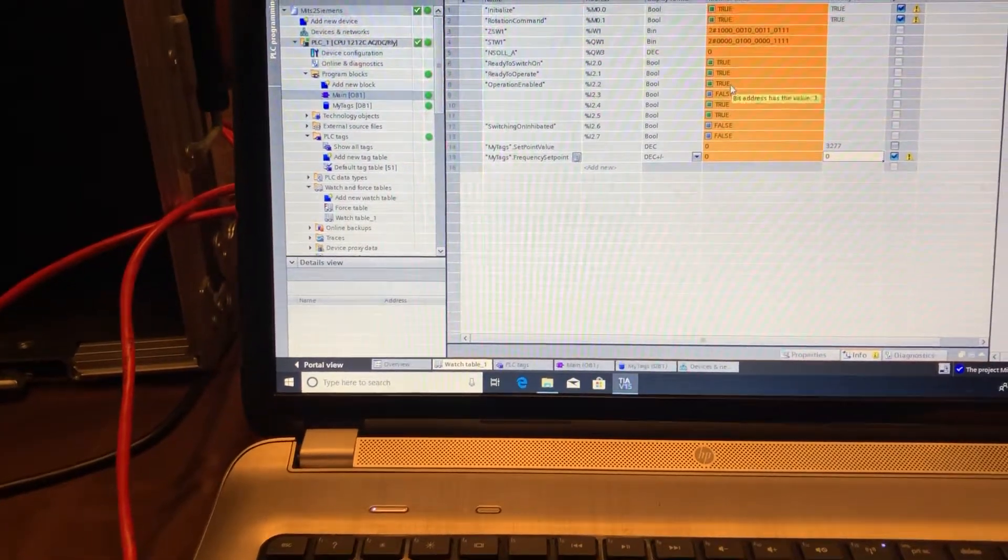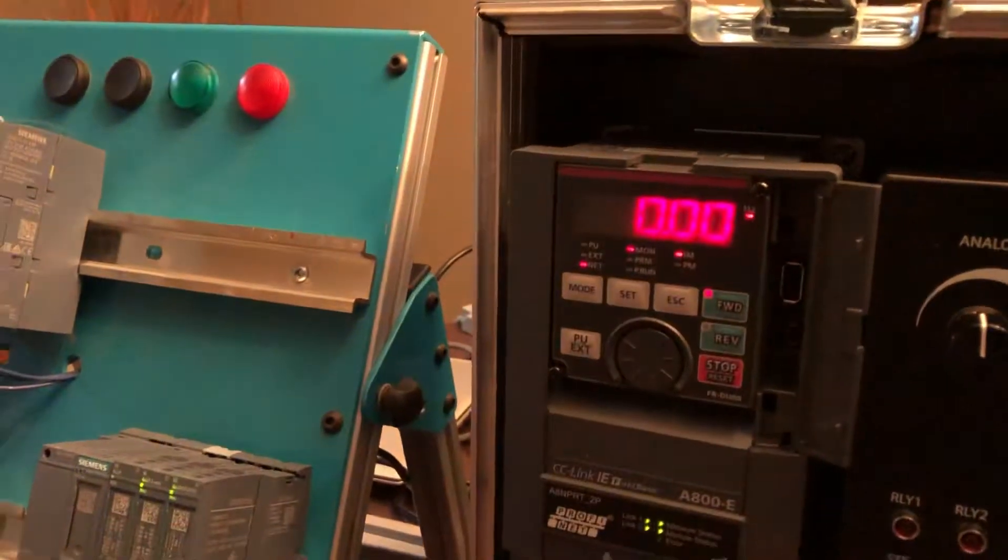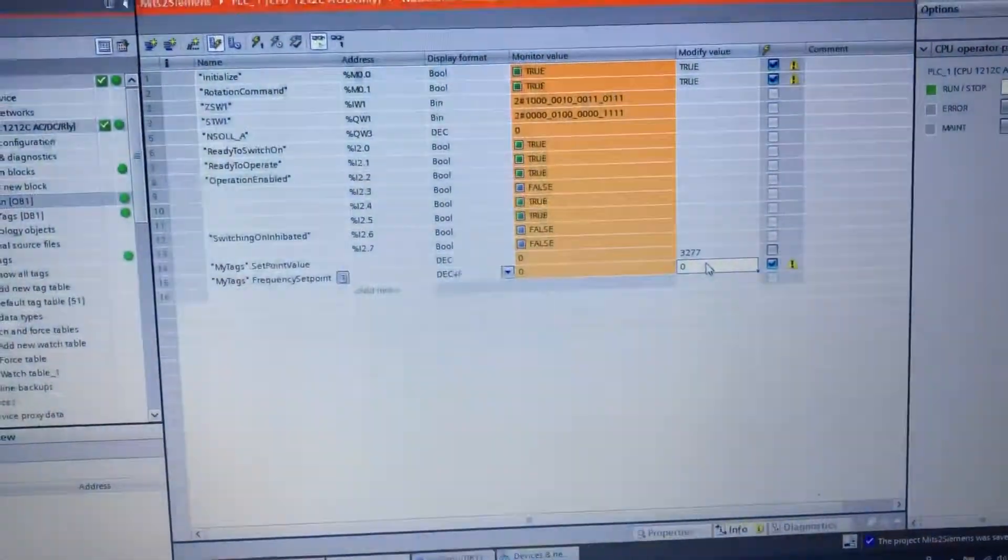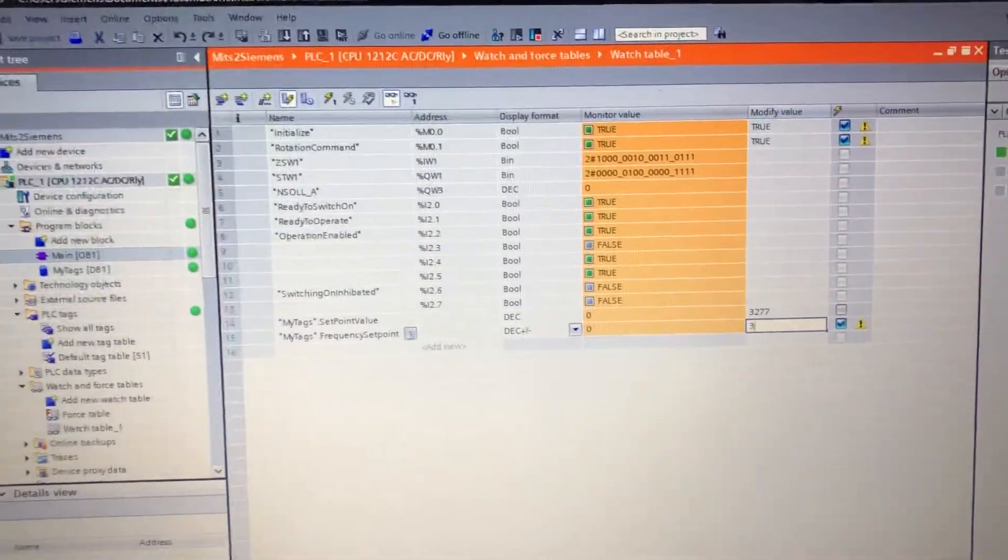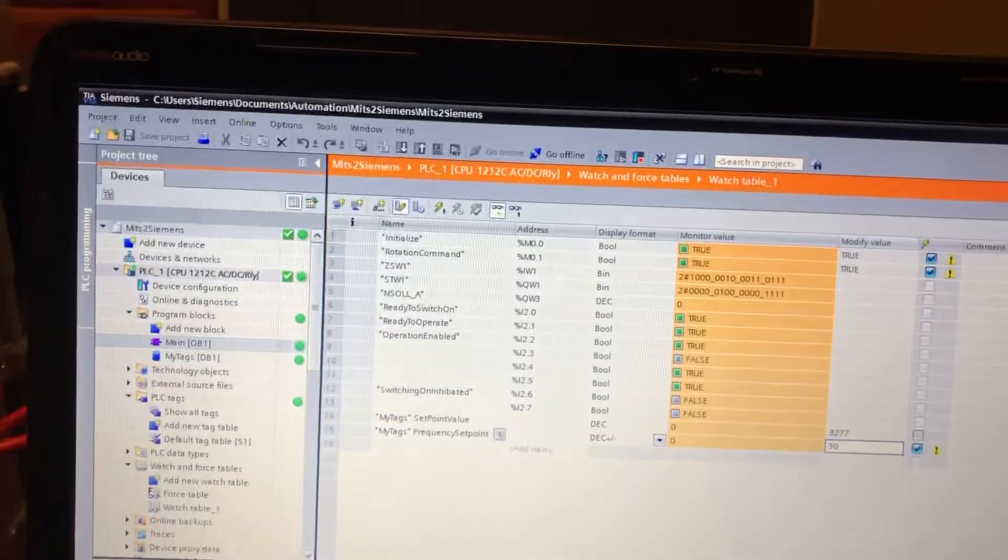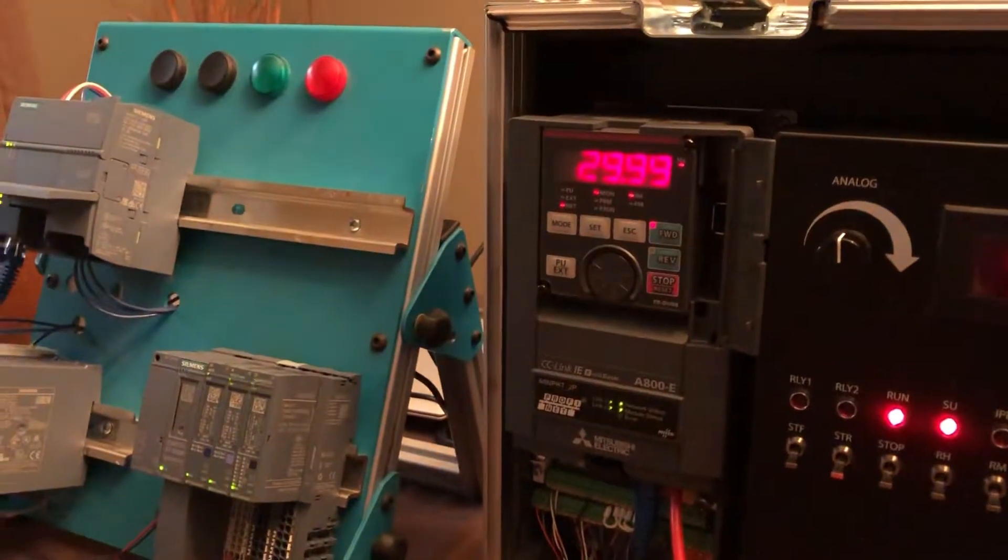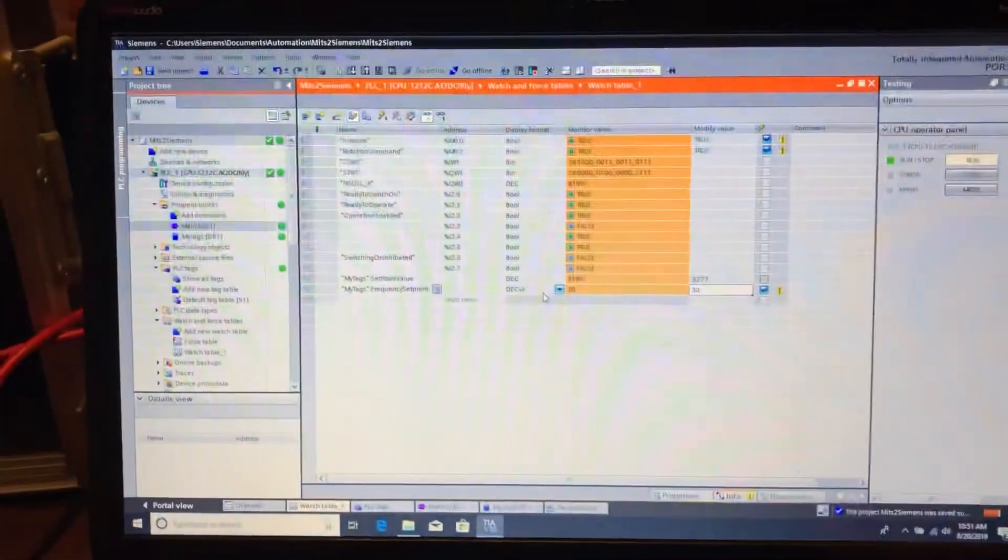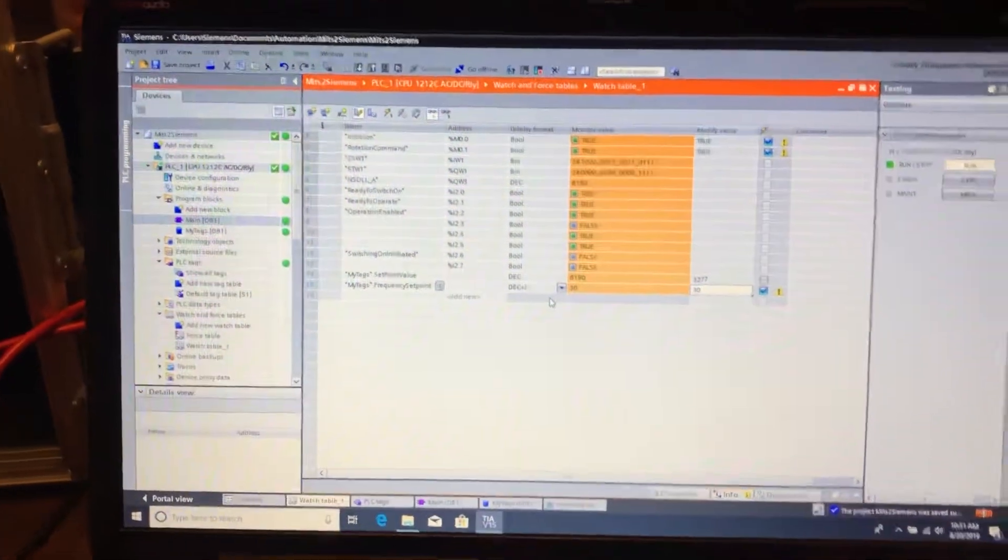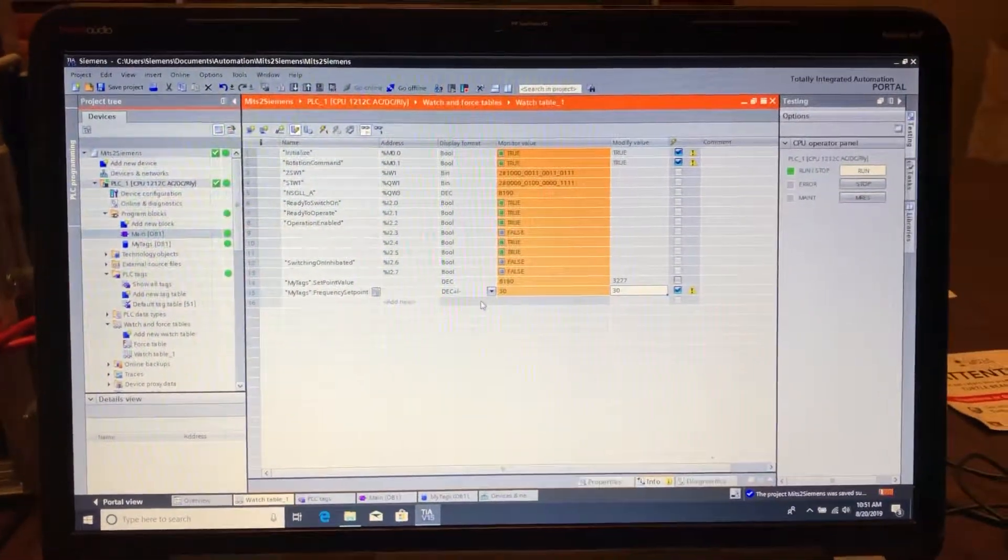We're able to change that frequency - you see it's at zero now. We'll go over here and enter in a new frequency like 30 Hertz, write that, and then the drive is commanded to 30 Hertz. There's more you can do, like acyclic data, but this just shows the basic interface and how easy it is to set up.